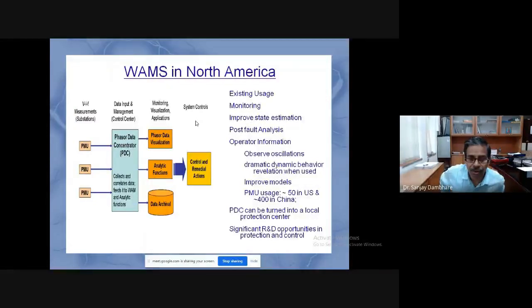So the PDC can also be used for protection. Now, the data sampling rate of these PMUs is not yet sufficient for primary protection, but they are used for secondary, backup protection. The current, voltage, and frequency data, the current and voltage phasors, meaning magnitude and phase angle, and the frequency data are collected at the phasor data concentrator. This is nothing but a computer where the data is received, and here the data is aligned with the same time tag, and then used for phasor data visualization, analytic functions, or data archival, and that is how control and remedial actions can be taken based on this data or this analytic.